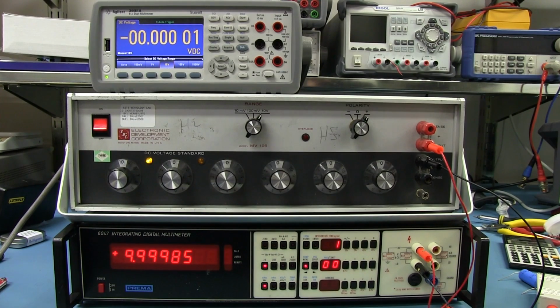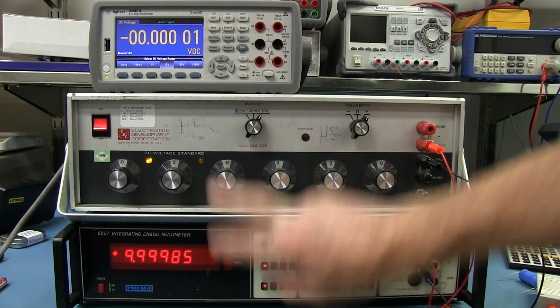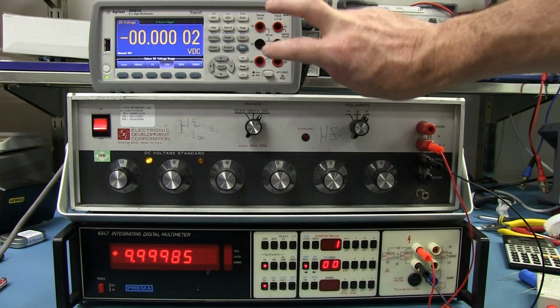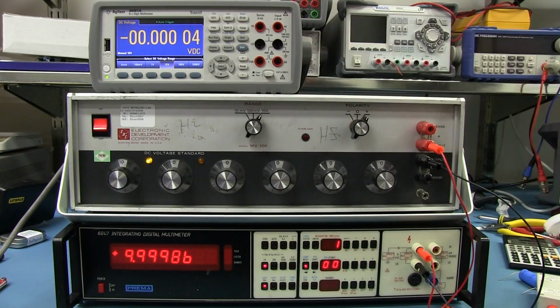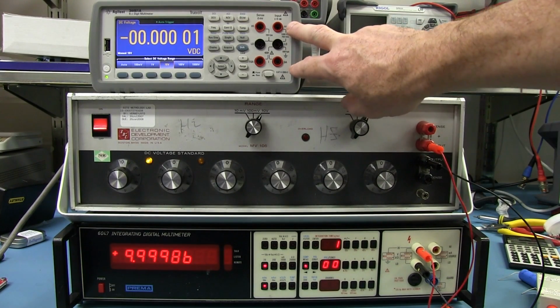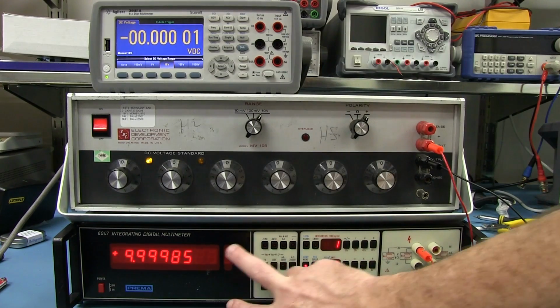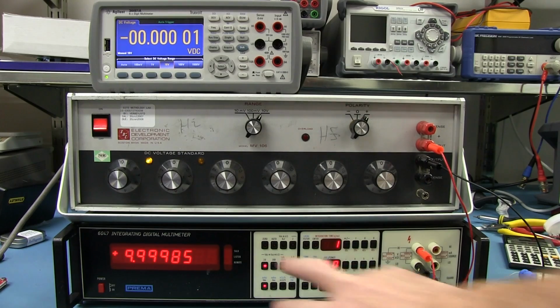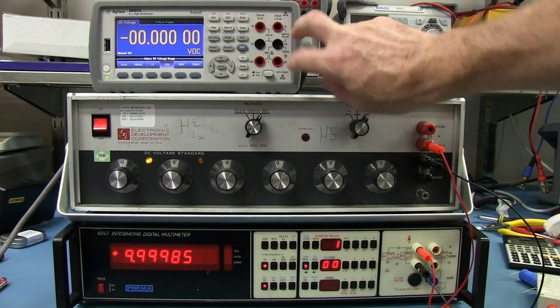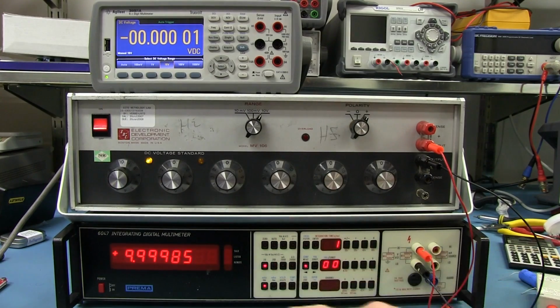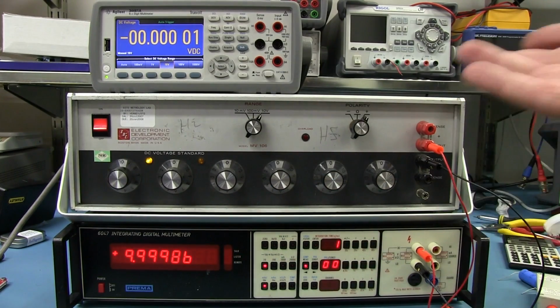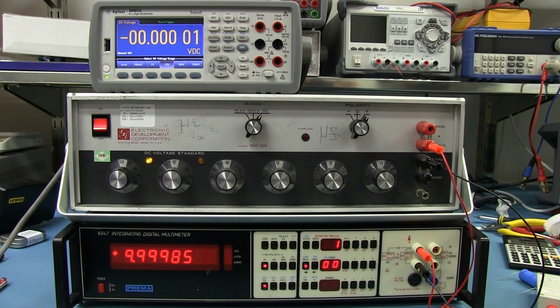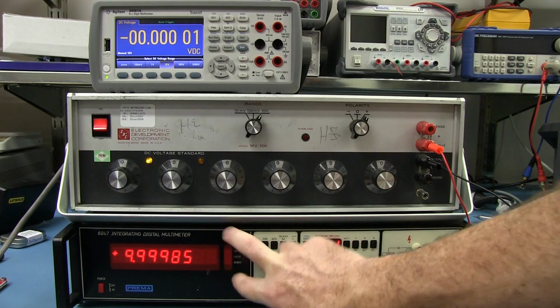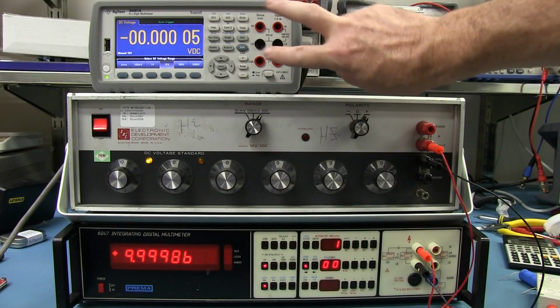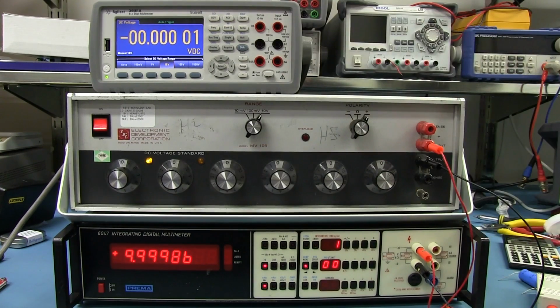So, you know, whether or not it's within spec, because we're talking the Agilent 34461A 6.5 digit multimeter, typically in the order of 0.005% accuracy in terms of like a 1 year accuracy. This Prema, 8.5 digits, 2 full digits more, pretty much, although this is 10,000 count. Anyway, this is 8.5 digits, goes up to 20, so it's 19999. And it's in the order of 0.0005%. So an order of magnitude, 10 times better basic DC volt accuracy spec than a top of the range 6.5 digit meter like the Agilent 34461A.